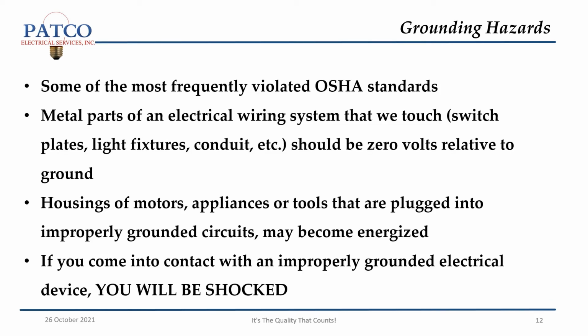Grounding hazards. Some of the most frequently violated OSHA standards. Metal parts of an electrical wiring system that we touch, switch plates, light fixtures, conduit, should be 0 volts relative to ground. Housing of motors, appliances, or tools that are plugged into improperly grounded circuits may become energized. If you come into contact with an improperly grounded electrical device, you will be shocked.